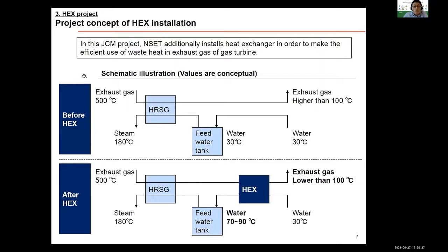The next slide shows a schematic illustration of the project. As I said, we installed a heat exchanger. We planned to make maximum use of gas turbine waste heat in the exhaust gas of the gas turbine in order to heat up boiler feed water. So after heat exchanger installation, we can confirm the reduction of the temperature of the exhaust gas, and we increased the feed water temperature.